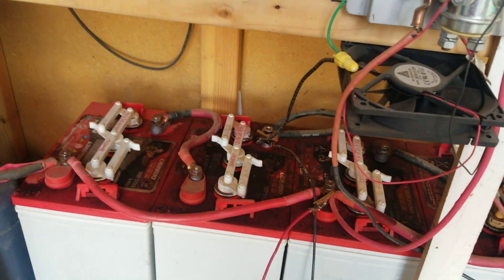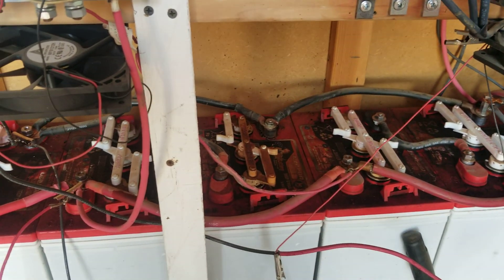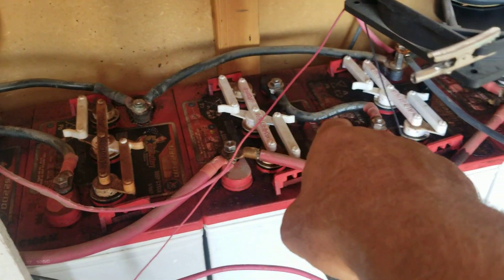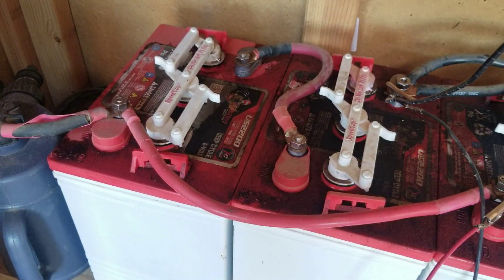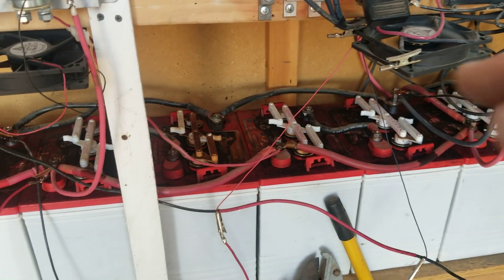I saw your connections on your batteries, though — they're acceptable. You usually want to try to keep your battery cables all the same length if possible. It's not necessarily super important; that jumper is a little shorter, but an inch or two isn't going to make much difference when you're using big wire like this — a two-gauge wire.